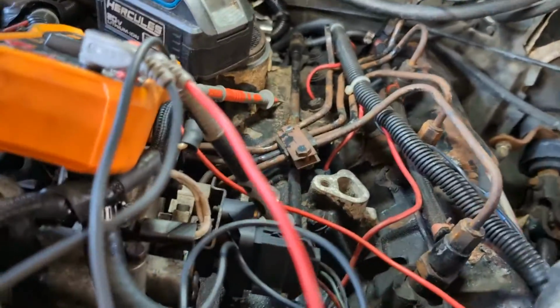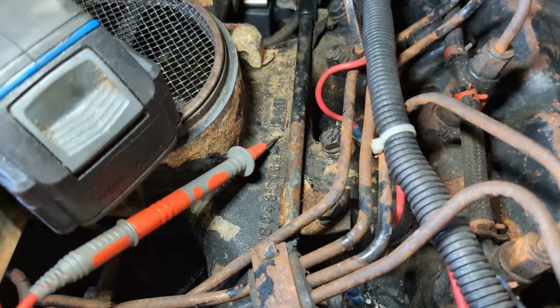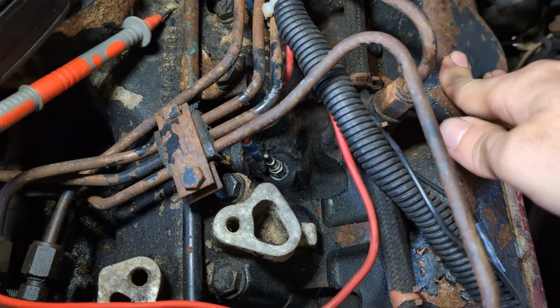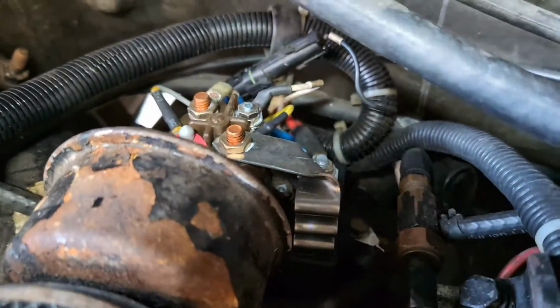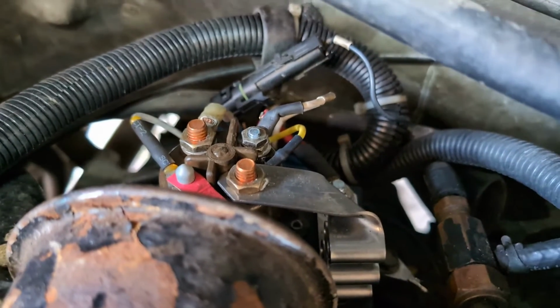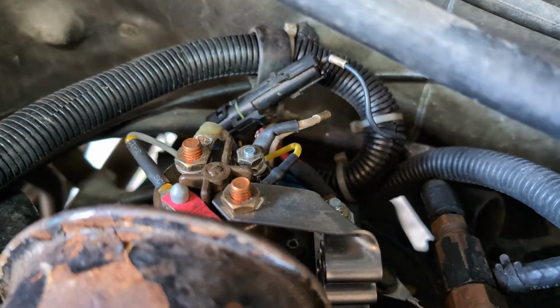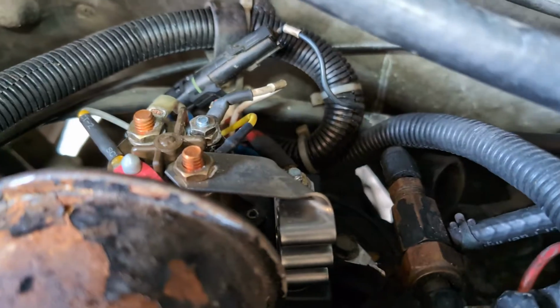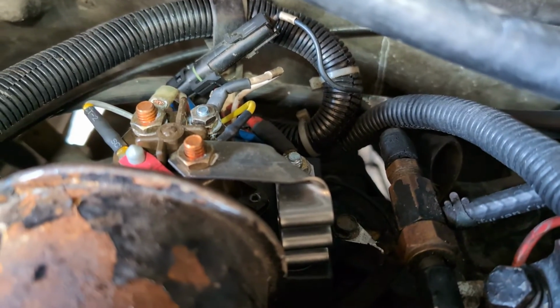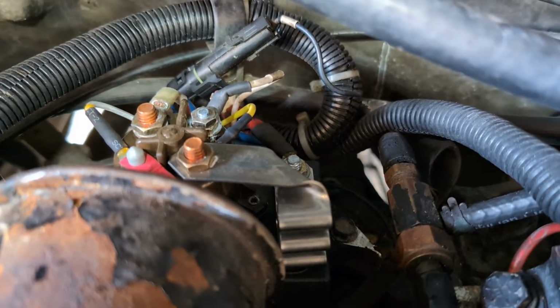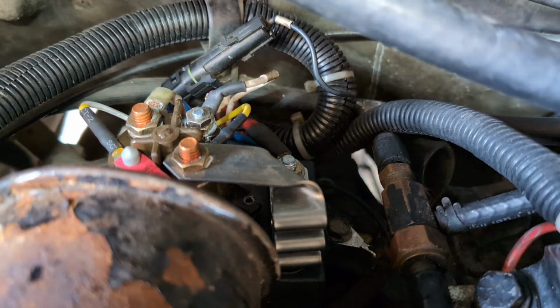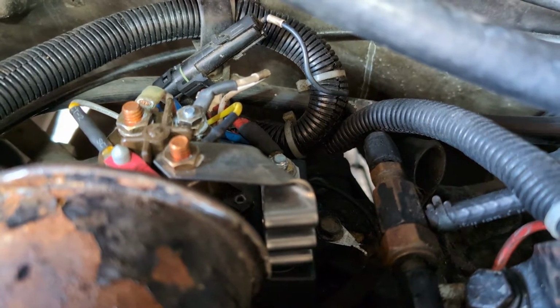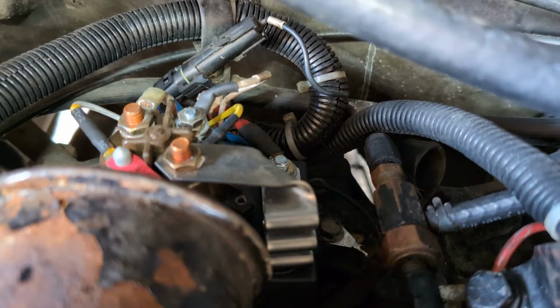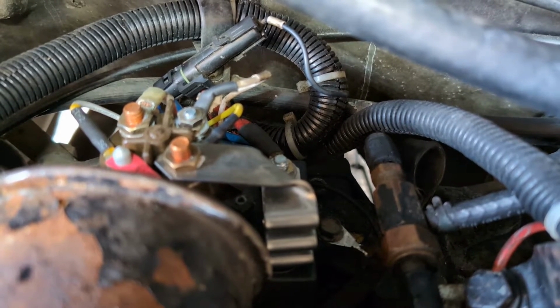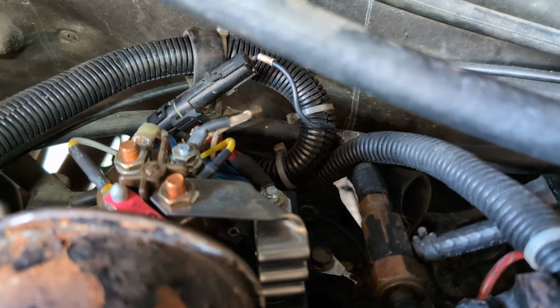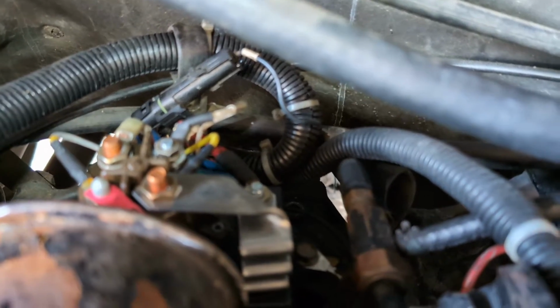Next thing we have to check: we've gone through our plugs and wires, and assuming those are fine, now we have to look at the glow controller and the relay. The next step is making sure the logic board, which is in that black base, has a proper ground, because it's a bit of electronics, and if it doesn't have a good ground, it won't work right.